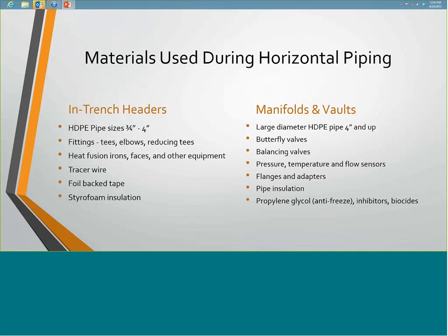We use tracer wire over the top of all that header pipe for tracing the field that's been installed, plus foil-backed tape, and occasionally you'll see styrofoam insulation installed over the piping for frost protection. When you get into the manifolds, connecting those headers to the manifolds in the vaults or in the building, you'll start seeing larger diameter high-density polyethylene pipe, 4 inches and up.